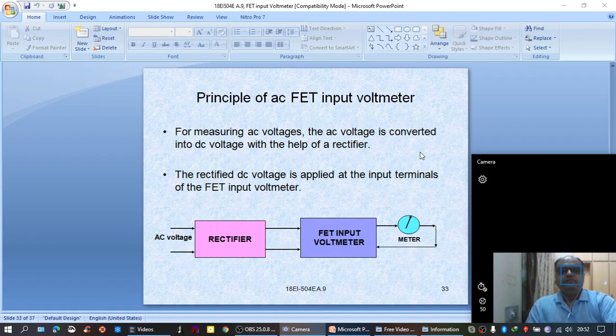For AC measurements, the AC voltage is first converted into DC voltage with the help of a rectifier. The rectified DC is applied at the input terminals of the FET input voltmeter. The only change is that a rectifier is added prior to the FET input voltmeter, and of course the meter is an average responding device. It responds to the average value of the input voltage.